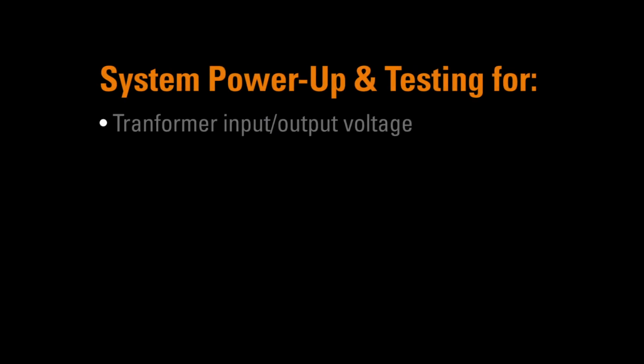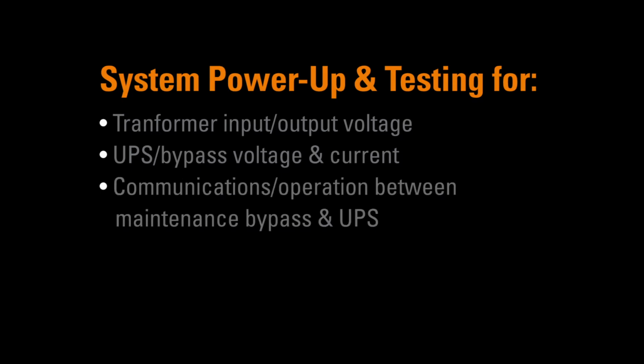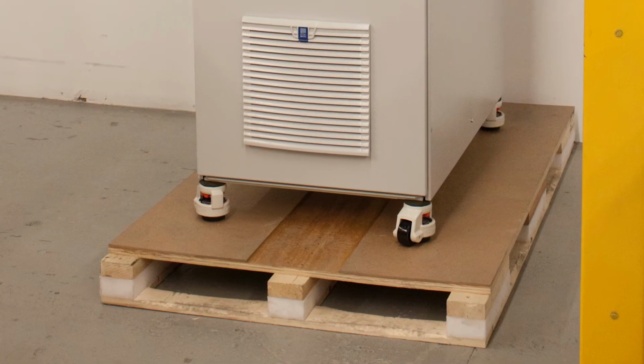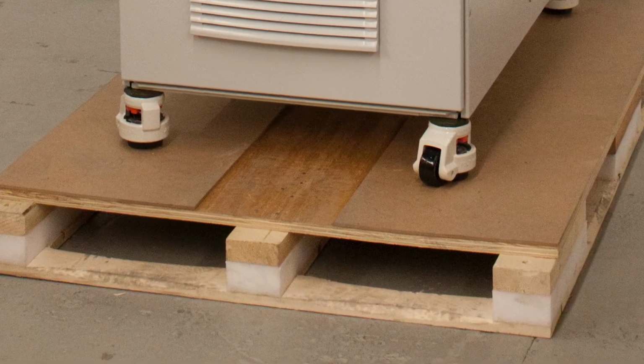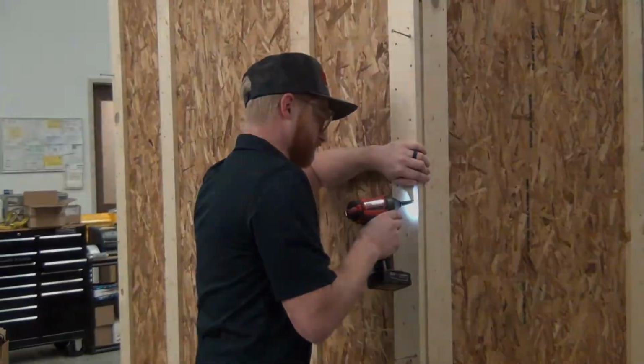transformer input and output voltage, UPS and bypass voltage and current readings taken at the output, communications and correct operation between maintenance bypass and UPS, functionality of the ventilation fan. The system was then secured to a custom shock-resistant pallet and crated for international transport.